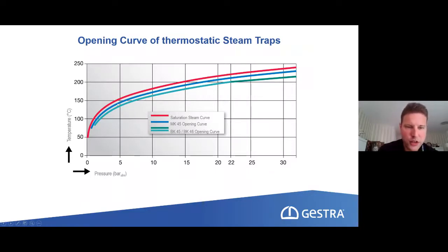And you can see that the opening lines are in the water area. So we have to cool down the condensate, which will reach the steam trap a little lower than saturated steam temperature, so maybe 1 or 2 Kelvin below saturation temperature. And then the steam trap will be tight and shut as long as we haven't subcooled the condensate to this temperature.